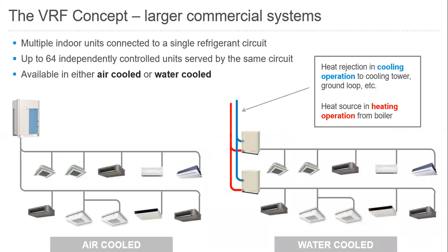So the VRF concept, as we look at larger commercial systems, we're known for having a single outdoor unit or a gang of outdoor units that have been linked together. We can have up to 3 air-cooled modules tied together to form a single system, and that single system has multiple indoor units downstream. As I mentioned earlier, those indoor units each have their own expansion device that opens incrementally, and that allows us to provide the right amount of heating or cooling capacity needed at any time in a single space. So we can actually have up to 64 indoor units on a single outdoor unit system.